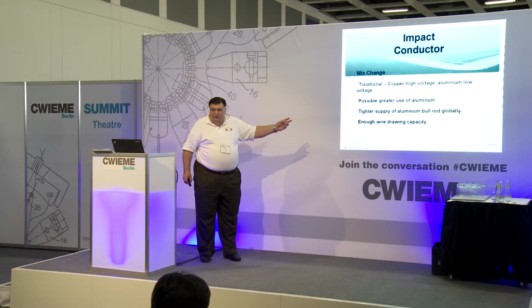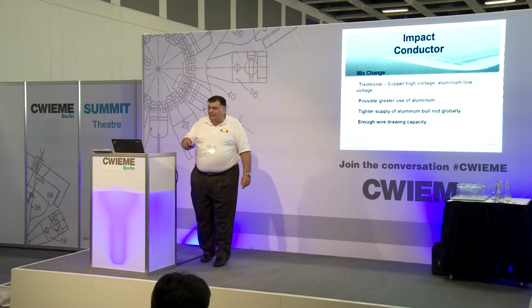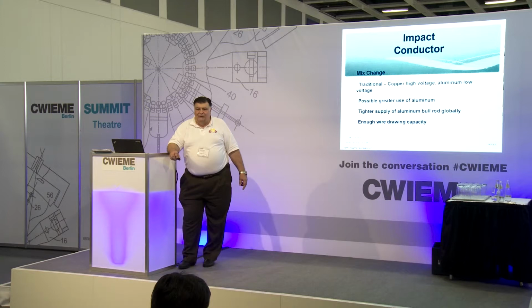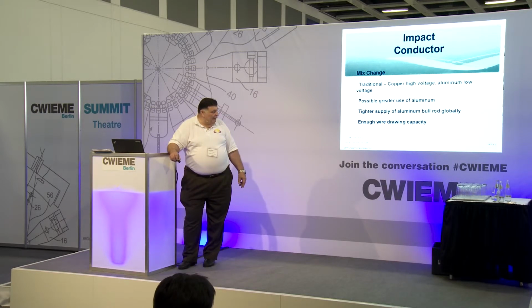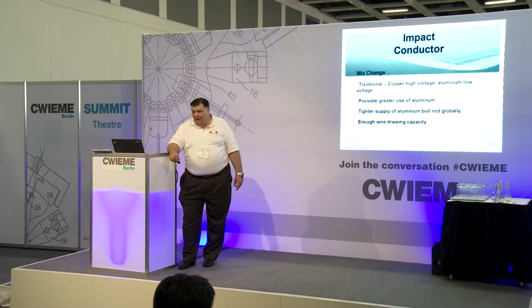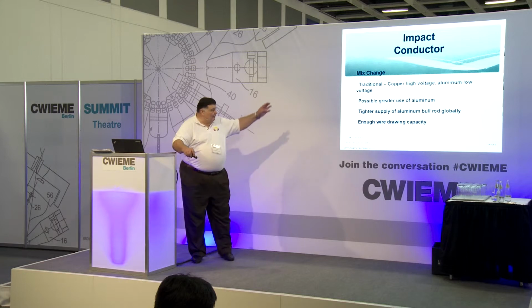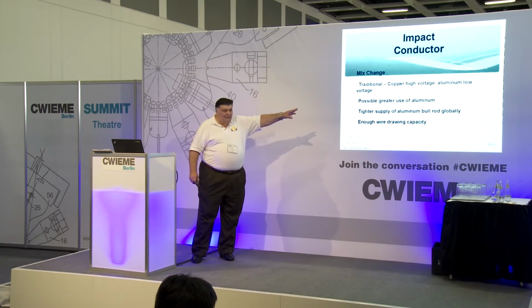Last year, toward the end of 2012, there got to be a tightness in the market worldwide for aluminum bull rod that was of the correct quality to be drawn into magnet wire for transformers. And outside of a couple of areas of the world, particularly the Asian market, that tightness of the correct type of bull rod is still in effect today. And they project it will have impact through next year. So if we're going to be pushing more toward aluminum, there's the next keystone that's going to be hit.